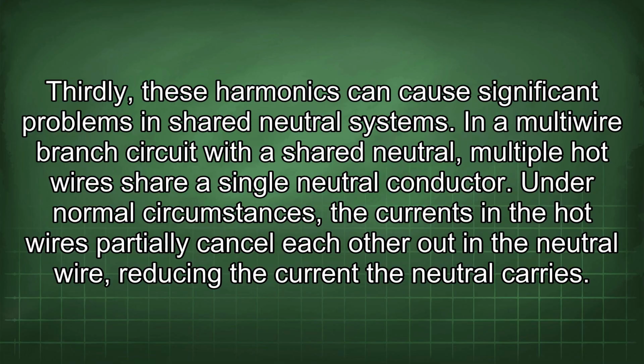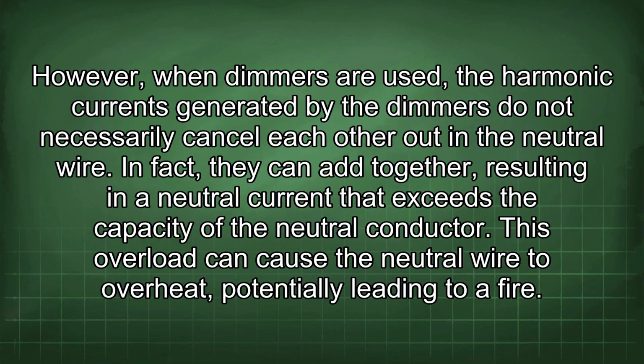In a multi-wire branch circuit with a shared neutral, multiple hot wires share a single neutral conductor. Under normal circumstances, the currents in the hot wires partially cancel each other out in the neutral wire, reducing the current the neutral carries. However, when dimmers are used, the harmonic currents generated by the dimmers do not necessarily cancel each other out in the neutral wire. In fact, they can add together, resulting in a neutral current that exceeds the capacity of the neutral conductor. This overload can cause the neutral wire to overheat, potentially leading to a fire.